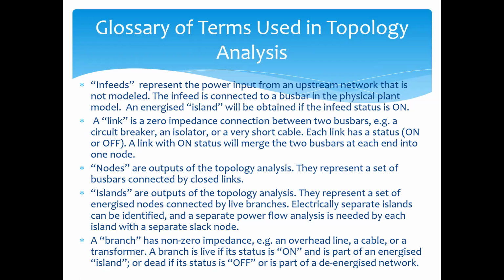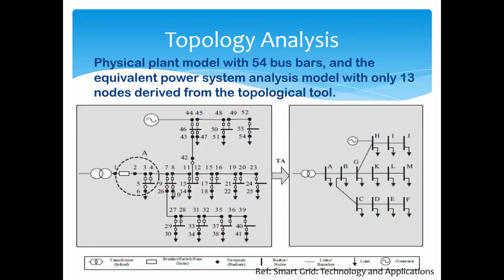A branch has non-zero impedance. Branch or line, it has non-zero impedance. That means it has impedance. For example, it's an overhead line or a cable or a transformer. A branch is live if its status is on and it's a part of an energized island, or dead if its status is off, or it's a part of a de-energized network. Here, between A and B, B and G, these sections are the branches. If their status is on, it's a part of the energized network. For example, if the I and J branch status is off, this is a part of the de-energized network, not a part of this energized network.